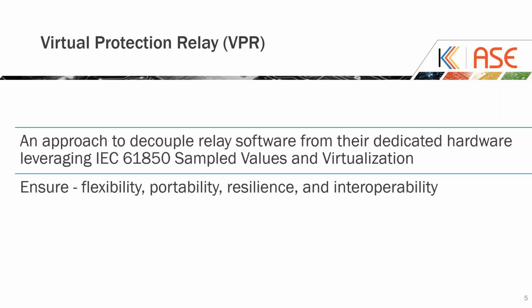VPR system can fit into any existing workflows, standards, or protocols, and shall have seamless integration with existing systems and devices. It can execute all protection schemes using IEC 61850 sample values and GOOSE. The IEC 61850 standard is a must for implementation of VPR. We have some slides coming up indicating the IEC 61850 substation diagram, where multiple IEDs are deployed and how that is converted to a virtualized platform.